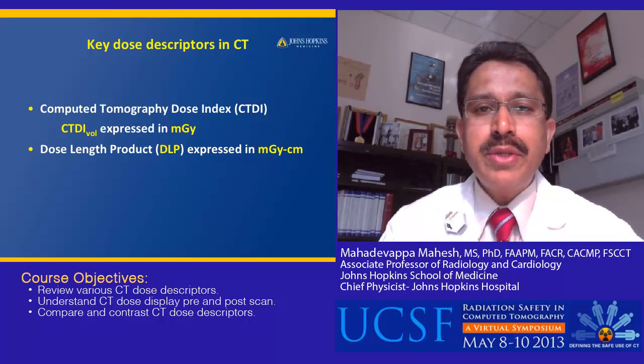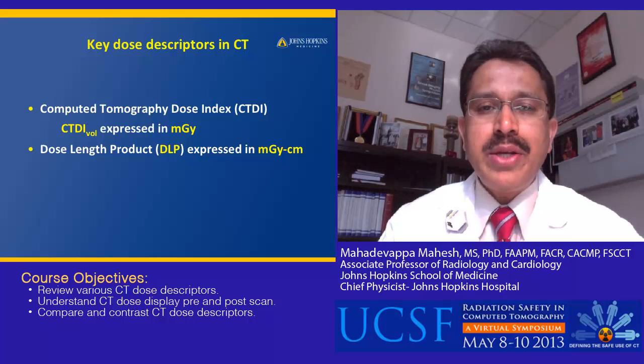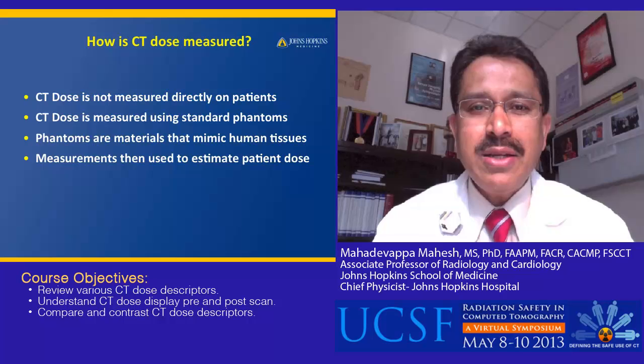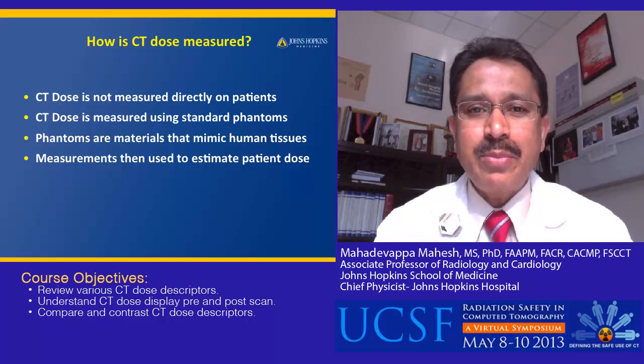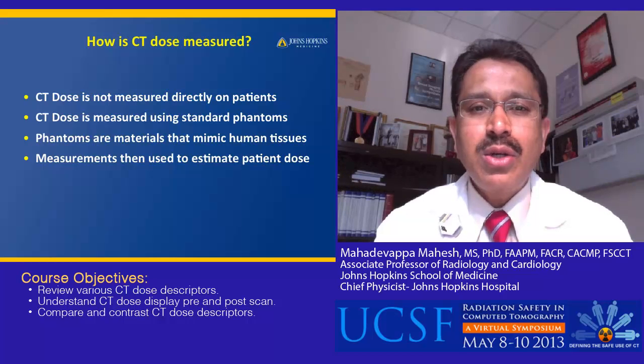The key dose descriptors in CT are the computed tomography dose index volume, with a unit of milligray, and dose length product, also abbreviated as DLP, with a unit of milligray-centimeter. CT dose is measured indirectly — we do not measure directly on the patient. In fact, CT dose is measured using phantoms, which are materials that mimic human tissues. By measurements done on the phantom, we use that information to estimate the risk to the patient.